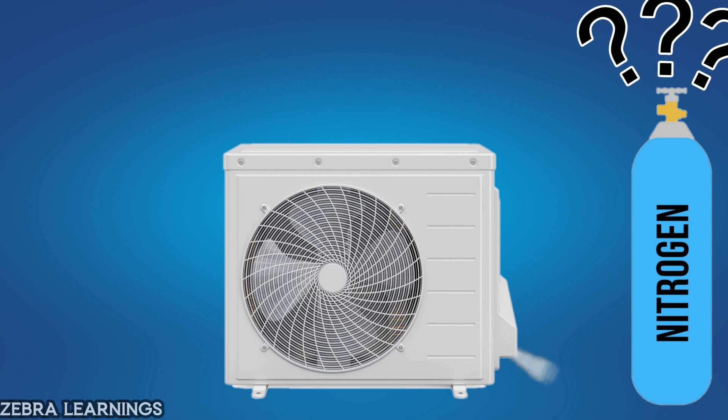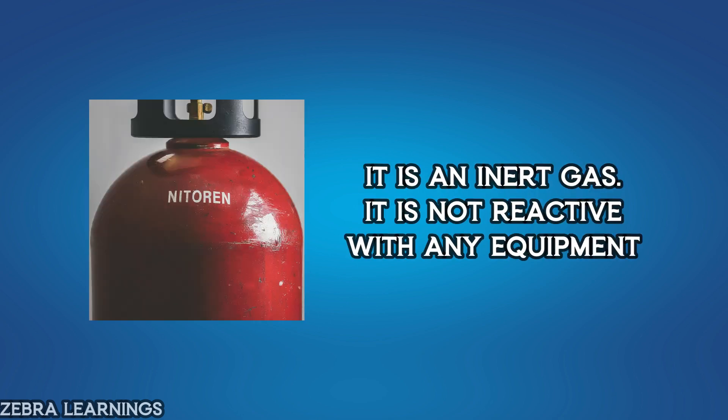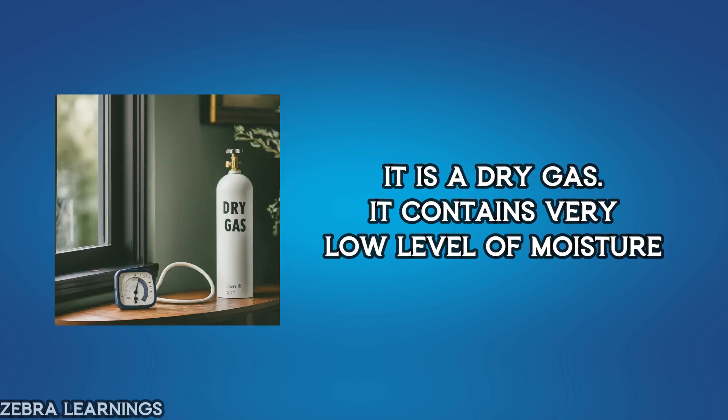Why is nitrogen gas used for leak detection in AC units? There are several reasons. Nitrogen is an inert gas, meaning it is non-reactive. Since it is non-reactive, it does not react with any component in the AC equipment. Therefore, there is no risk of using nitrogen gas in an AC unit. Also, nitrogen is a dry gas, meaning it contains very low levels of moisture. This prevents corrosion from occurring in the equipment.